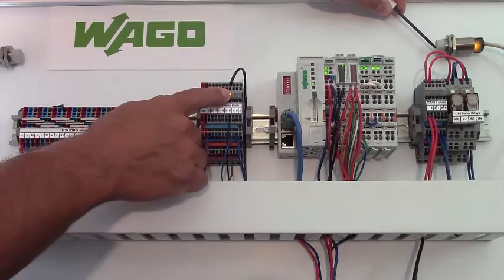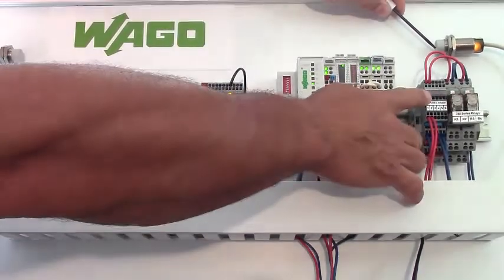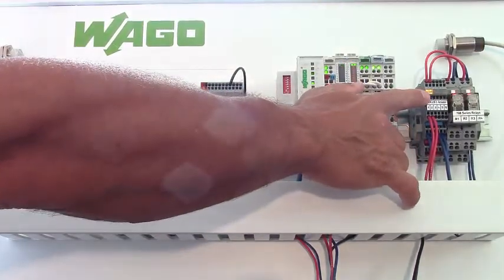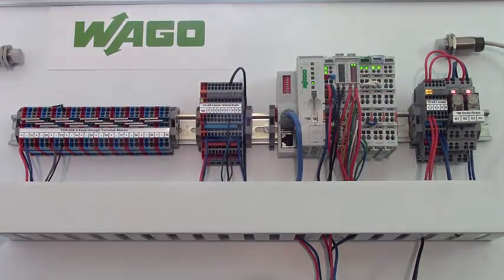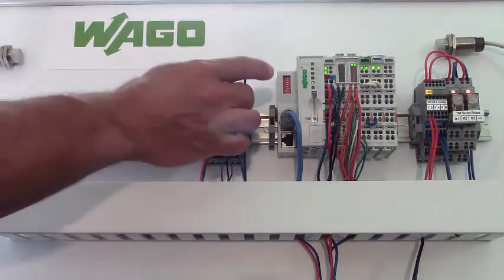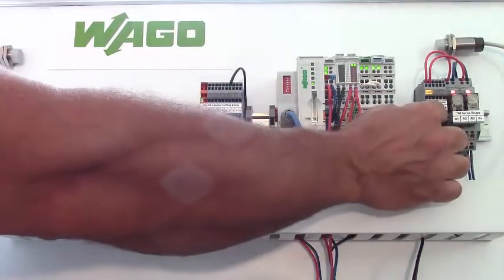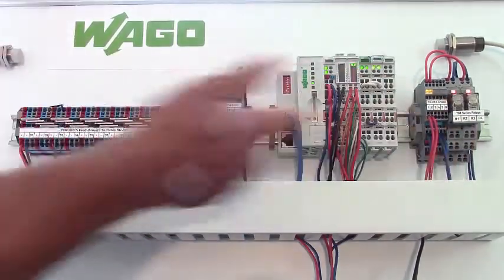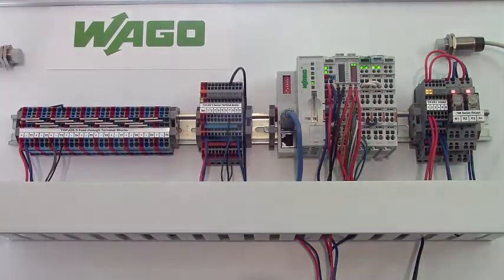Again, you see the signal here, but you'll also see on the actuator blocks when it's being energized. So we're getting another clear indication, not just on the sensor side but the actuator side, where we have clear indication whether or not the circuit is energized.